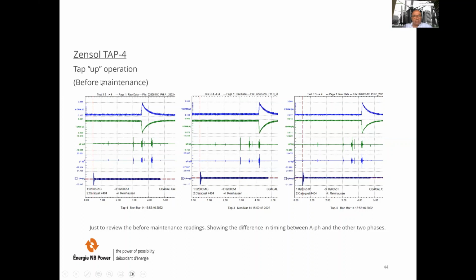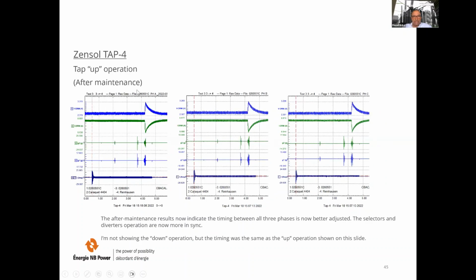So for the tap up, just to review the before maintenance reading, it shows the difference in timing between A phase and the other two phases, as you can see here. And after maintenance, the results now indicate the timing between all three phases is better adjusted, and the selectors and diverter operations are now more in synchronization. I'm not showing the down operation, but the timing was the same as the up operation shown on this slide.